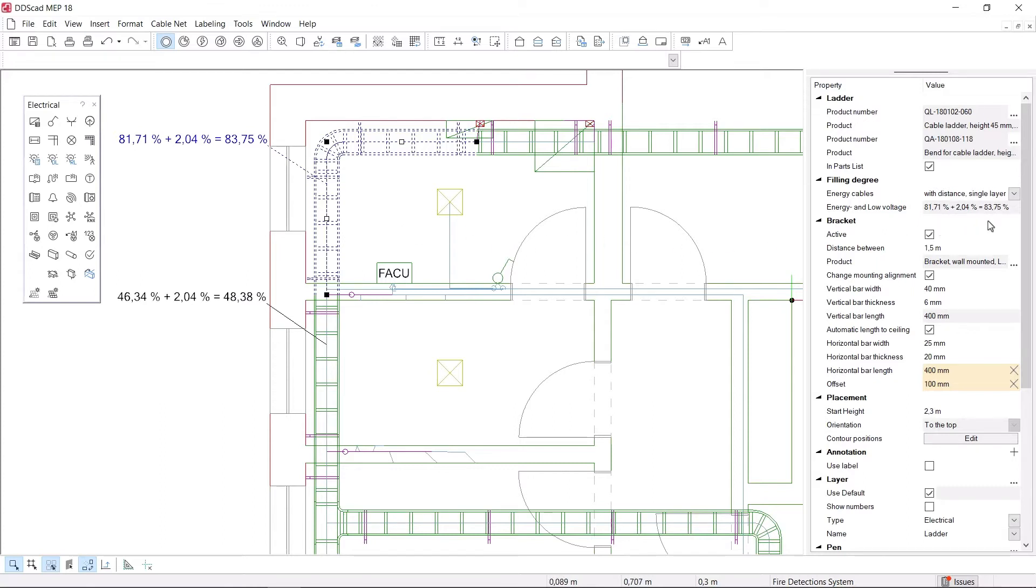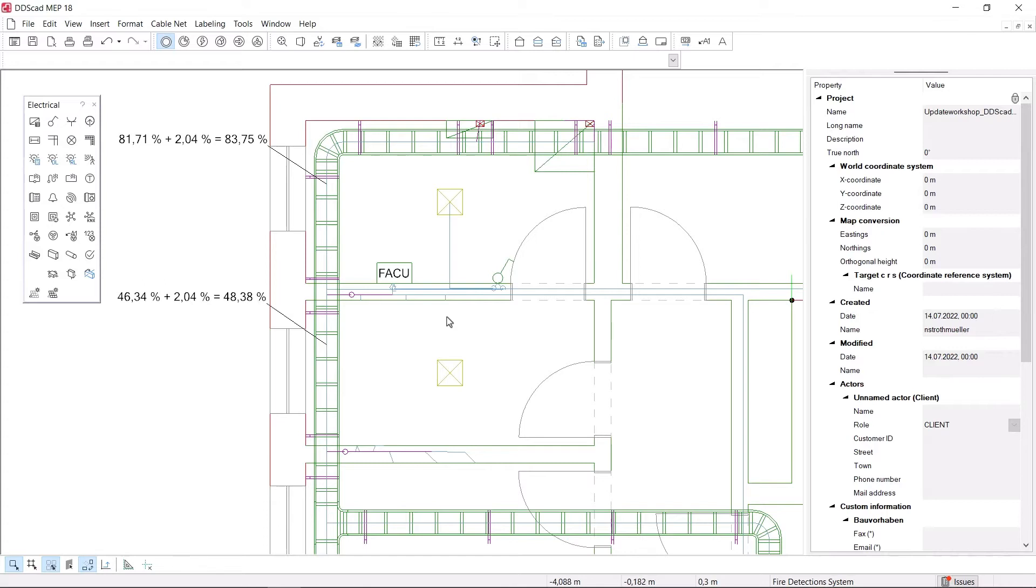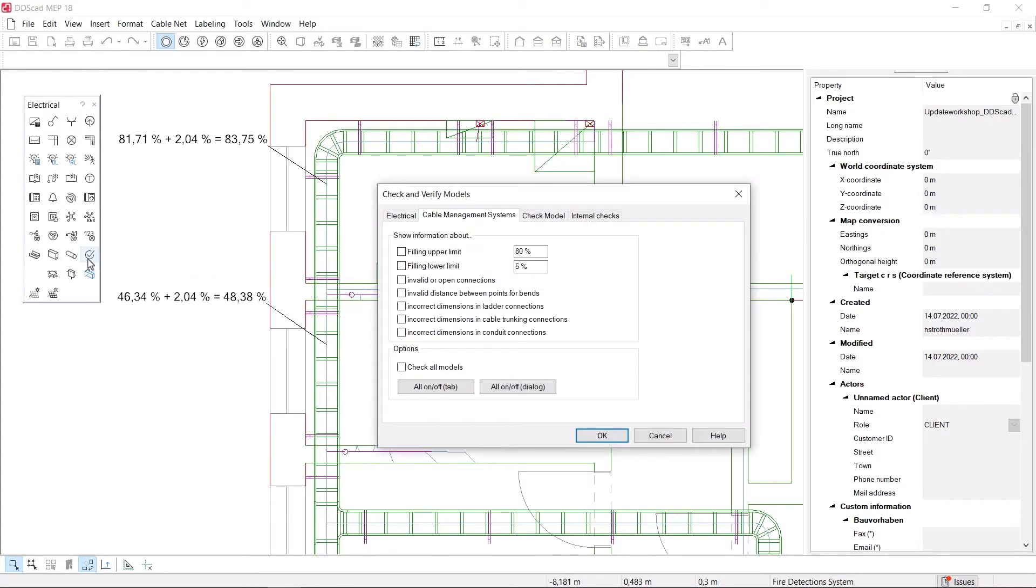The filling degree calculation checks the individual sub-segments of the cable management system. The detailed result is clearly displayed directly in the properties window. This allows you to identify critical parts of the system and adjust components as necessary.